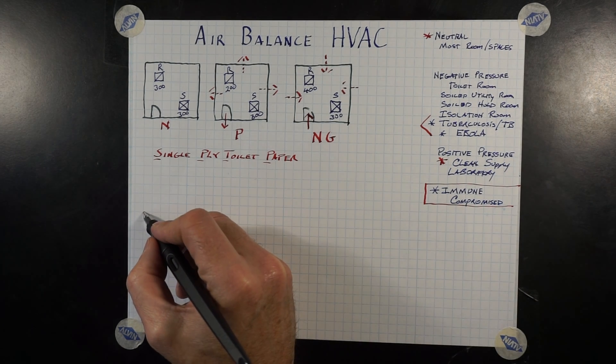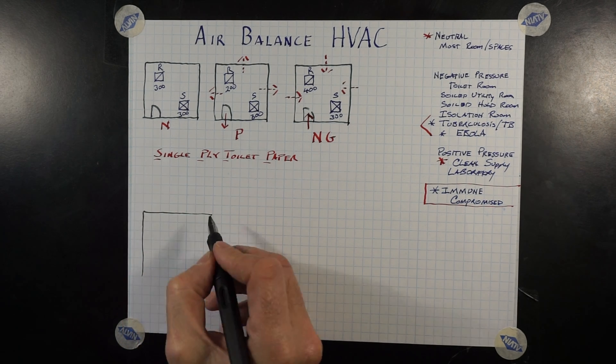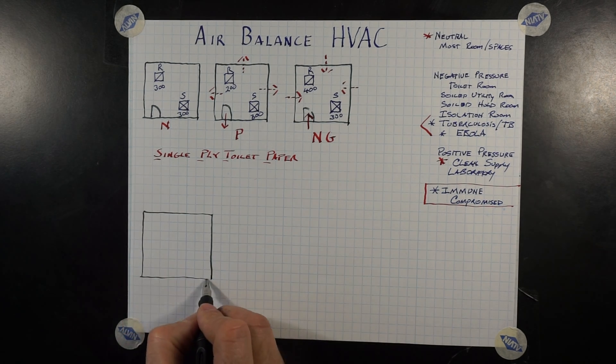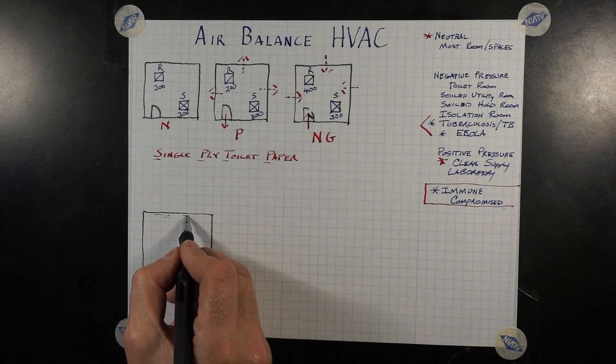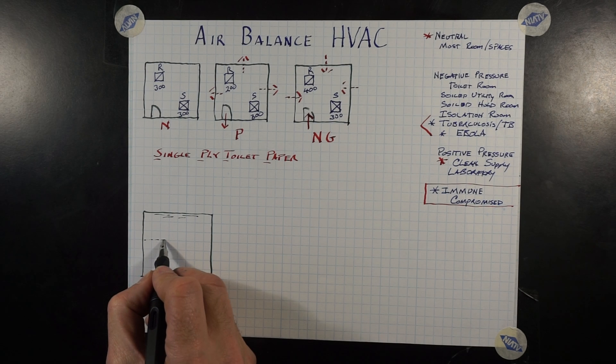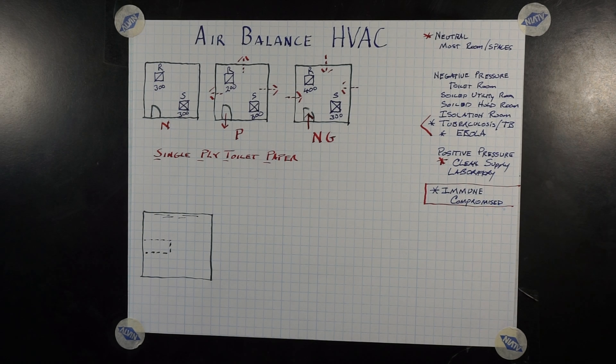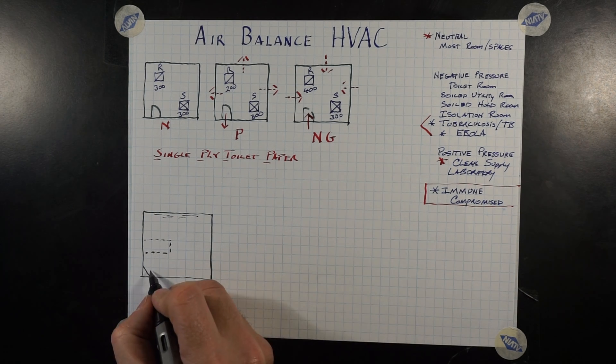If the toilet paper does not move, that is neutral. If the toilet paper is being blown out of the room, and everything is tested in relationship to the corridor, that means that room is positive. If it's being sucked into that room, that means that room is negative. So any toilet room, gang toilet, or office toilet space should always be negative in relationship to the space surrounding it.